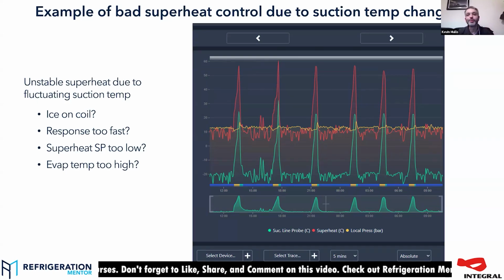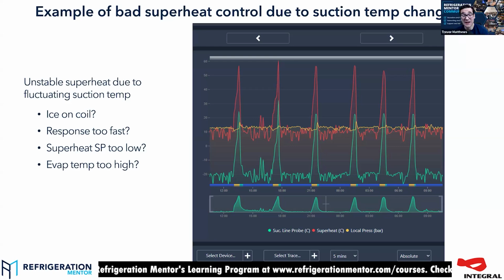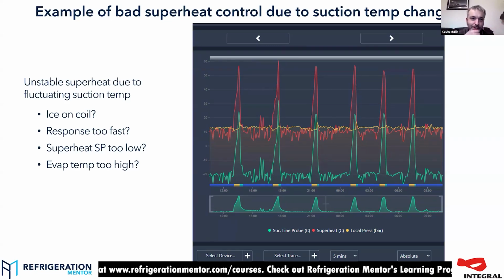And you've got to balance how you do your start opening, especially if you're using probes, and how you do your problem opening, with making sure the coil can get away again after a problem, but not so much. It's really tempting to say, go start opening 75%, because I'll definitely get the coil away then. But it's that iced up coil thing. It's flooding it right out. And exactly, all the controllers are the same. They'll all ignore superheat for a startup period, because they have to, for the probe issue. They've got to ignore the superheat to get the inlet probe cold. And they've got to allow that flexibility, but you've got to use that with some caution.